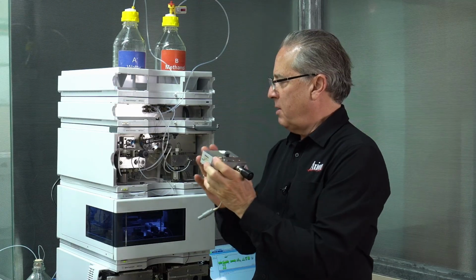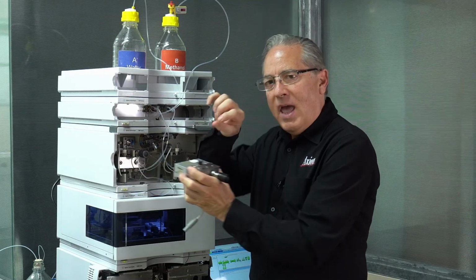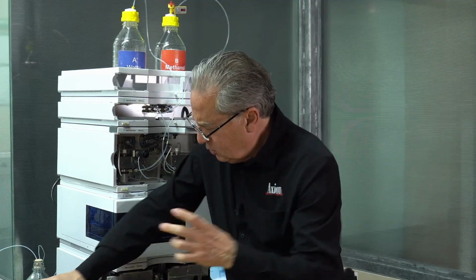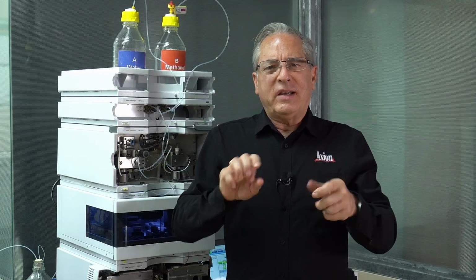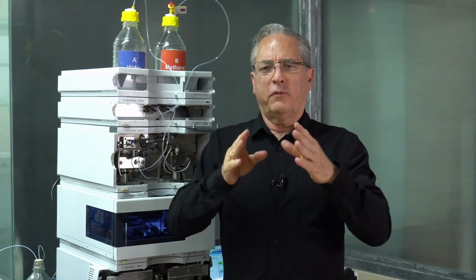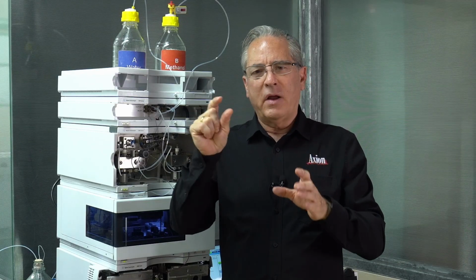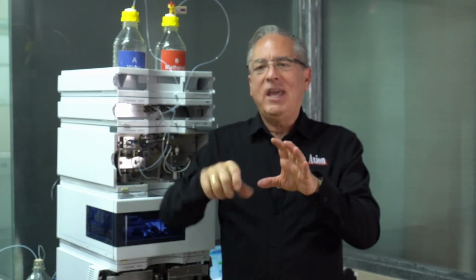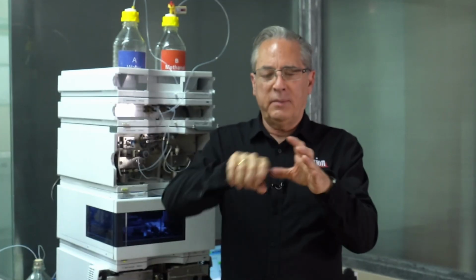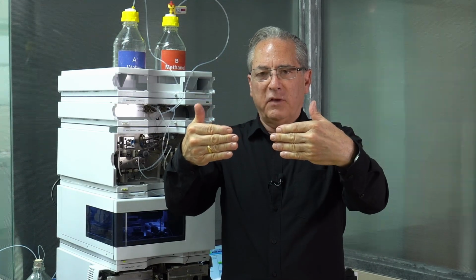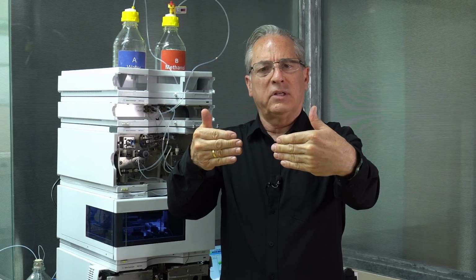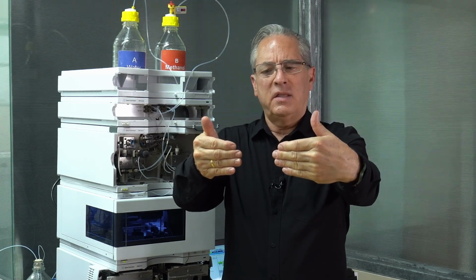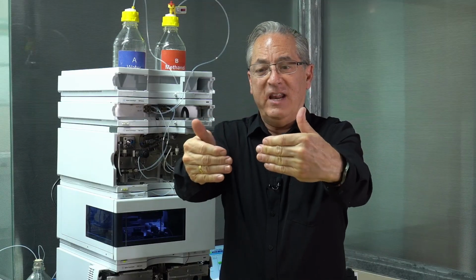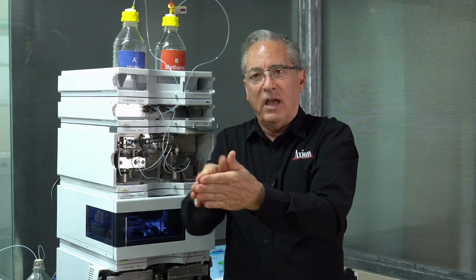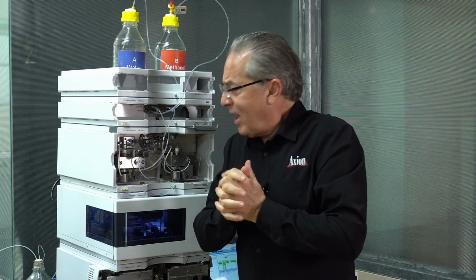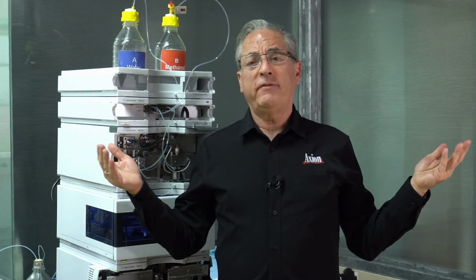And then we just put them back on the rail, all the way back in. And when you tighten the screws, those two long screws, you want to tighten them stepwise. You're going to notice that when you put it on, there's a spring in there and it's cocked back maybe half an inch. So you keep tightening each one, like tighten this one 5 times and this one 5 times. Keep going back and forth, because you'll find that one is totally tight and the other one's a little loose. So you tighten it up, and then the first one's loose, and then the second one's loose. That's because you're stepping it in, and eventually you'll get stainless steel against stainless steel, and you'll know it's tight. Okay, that is the number one procedure you're going to have to do on an HPLC pump.